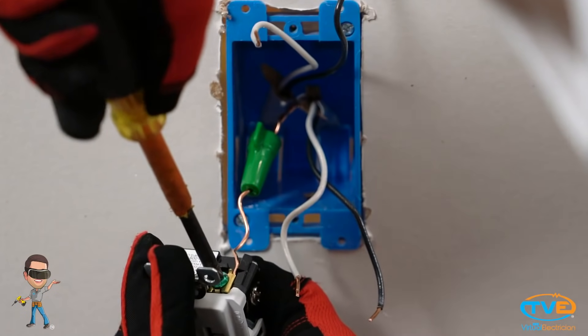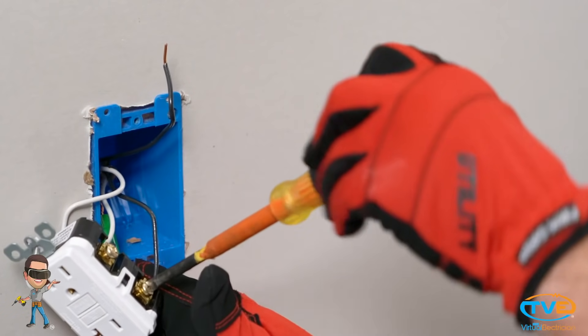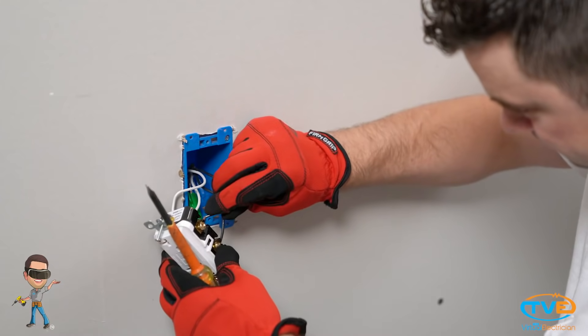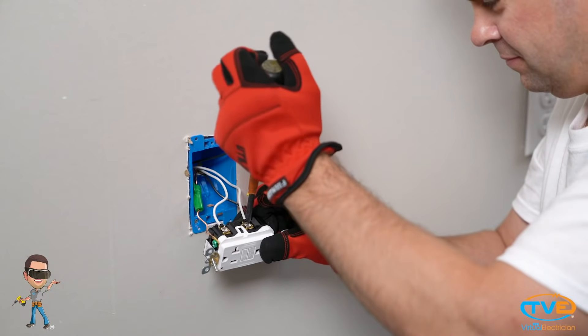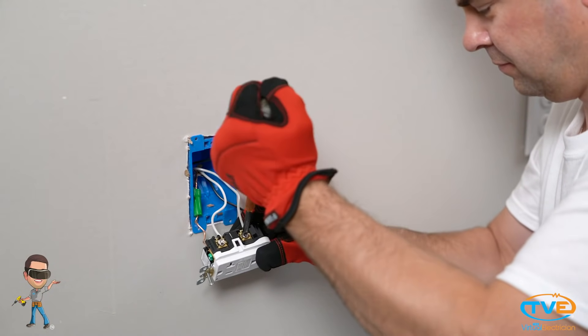Cap that wire with a wire nut, then turn back off the circuit breaker. Now you're ready to connect your device. Connect the bare wire to the green screw, install the line wire on the line terminals, and install the load wires on the load terminals.